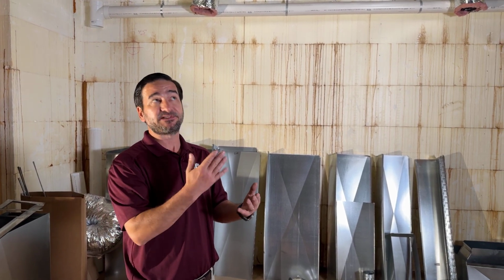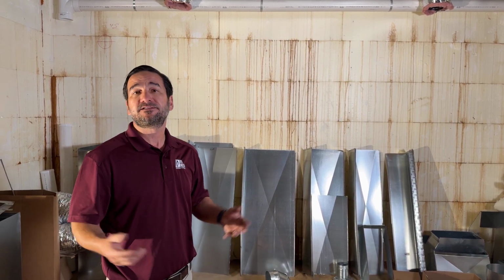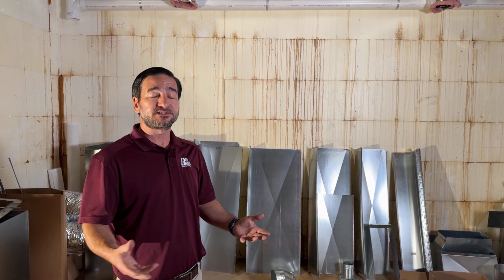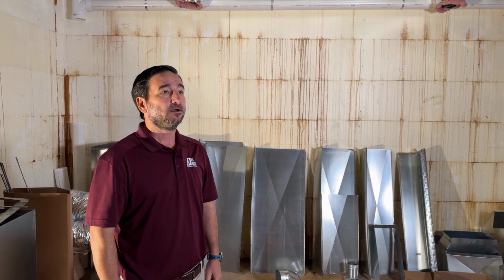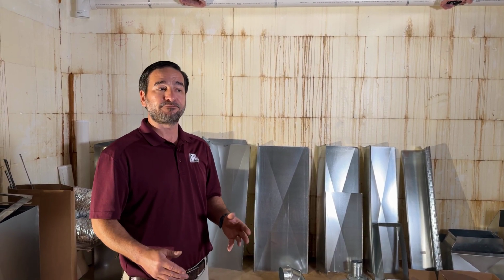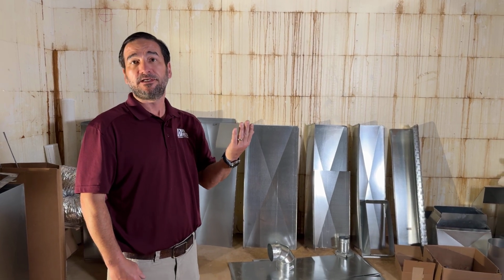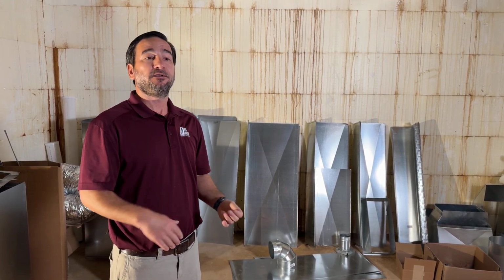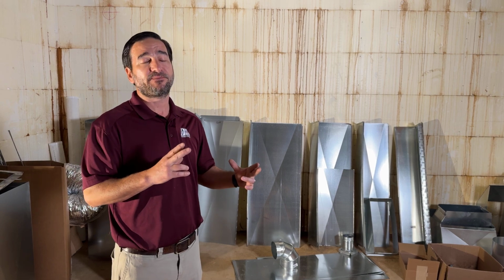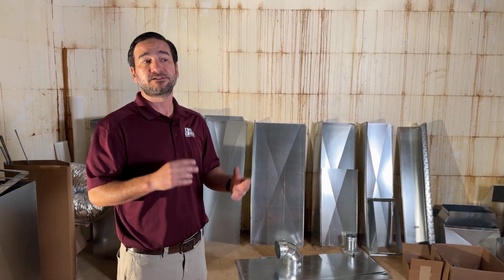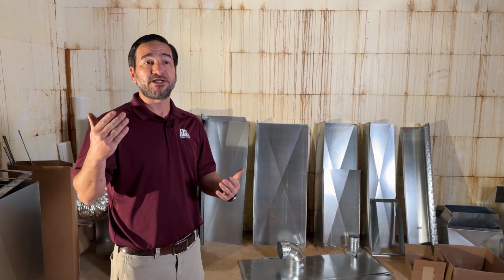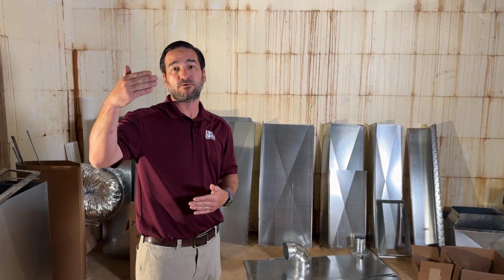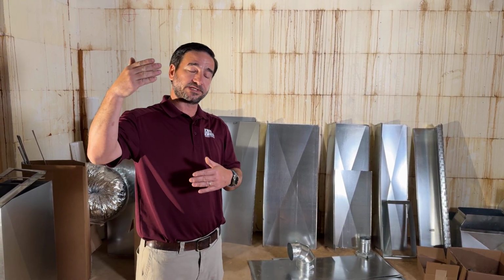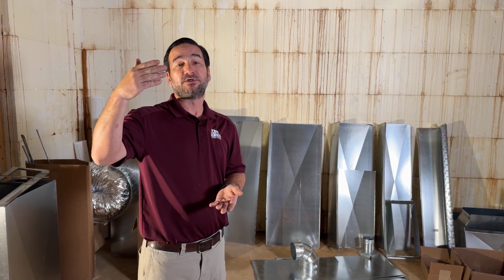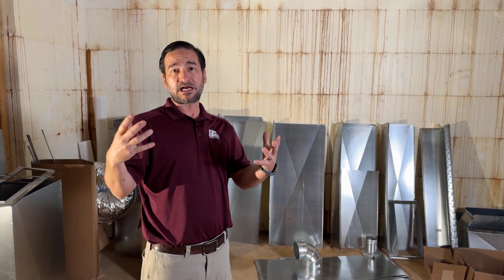We have pipe dampers. So if you had a retrofit application, let's say you have a two-story house in the Highlands or an older home where the basement's unfinished, you can get to all the ductwork. We can go into that house and we can put dampers in each branch duct. And then we have one zone control panel, hook different thermostats to it. The zone control panel is the traffic director, if you will. So if it's a summertime situation and the first floor is comfortable, but the second floor still needs cold air, all those first floor dampers will close down. The system will continue to run and deliver air to the top floor.